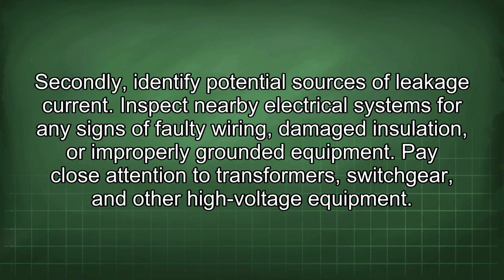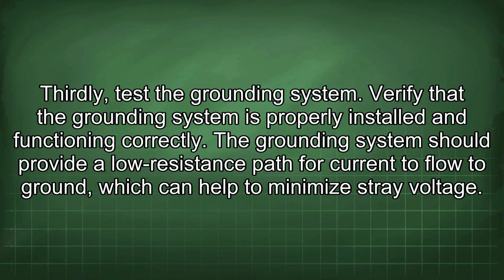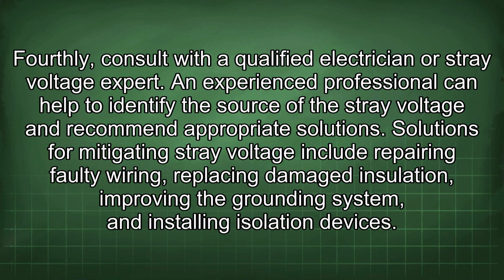Secondly, identify potential sources of leakage current. Inspect nearby electrical systems for any signs of faulty wiring, damaged insulation, or improperly grounded equipment. Pay close attention to transformers, switchgear, and other high-voltage equipment. Thirdly, test the grounding system. Verify that the grounding system is properly installed and functioning correctly. The grounding system should provide a low-resistance path for current to flow to ground, which can help to minimize stray voltage. Fourthly, consult with a qualified electrician or stray voltage expert.